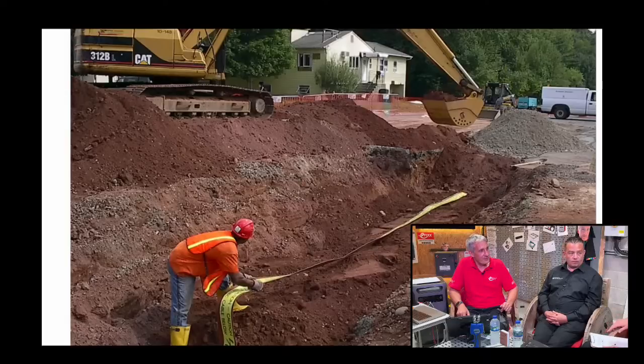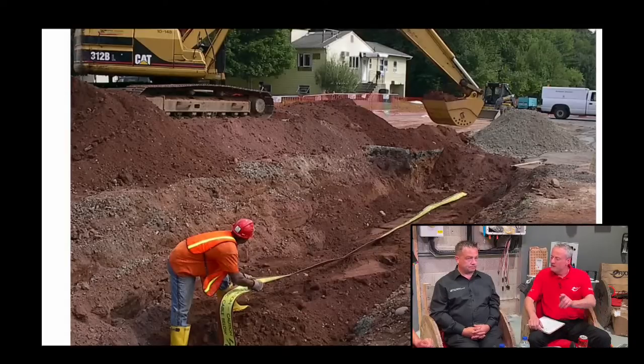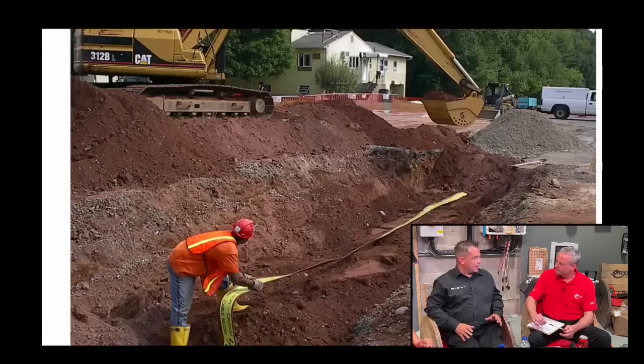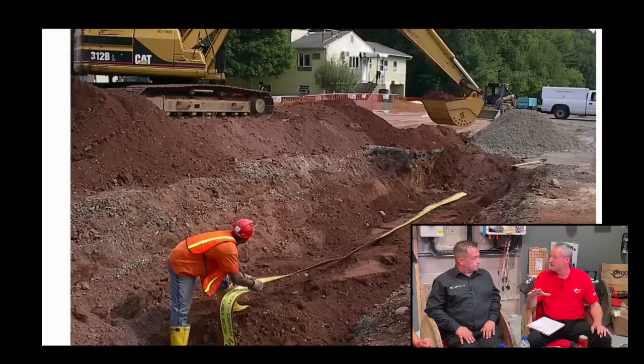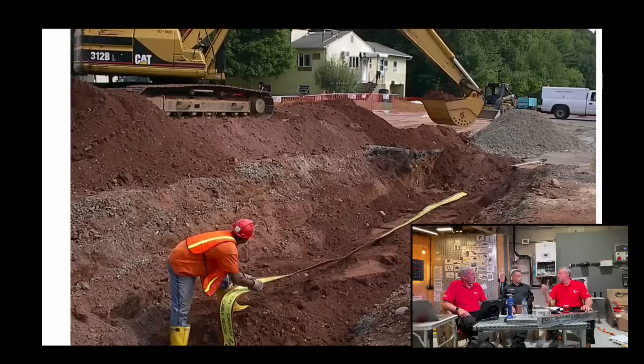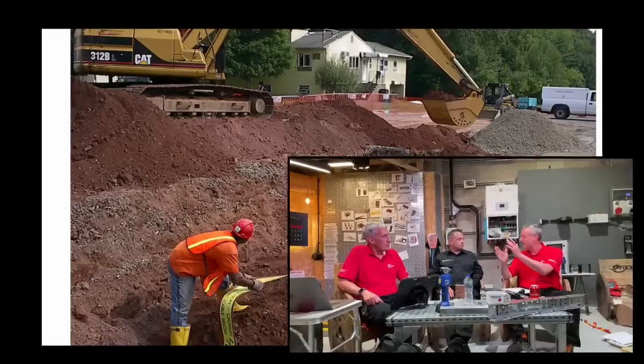So let's soak this one in. Before it was a cable in a duct in the ground, and now a cable in the ground with no duct has got a new column? Yeah, so the column that was there before was just for buried cables - that's now for ducted cables, and there's a new column for buried cables. For me personally, there's an exam question on the 8202-30, level 3, which asks you to use the resistivity of soil and other technical things, so now there'll be an extra column.